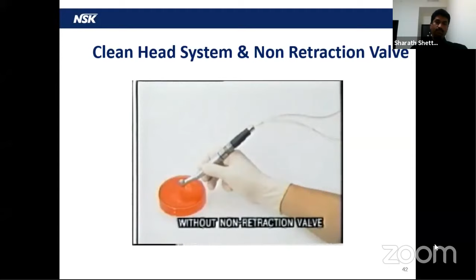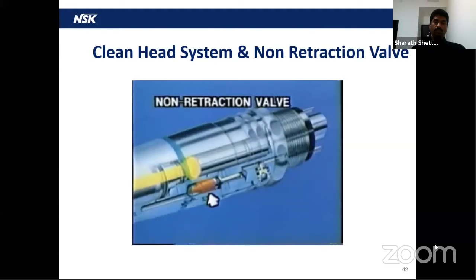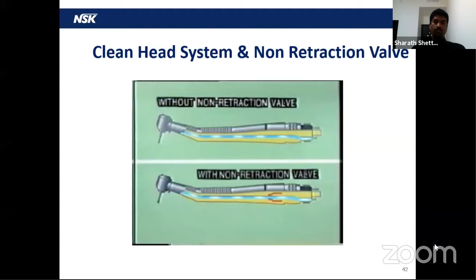The test you are now seeing is conducted without the non-retraction valve. You can see clearly, the retracted water, colored in red, is drawn back beyond the handpiece into the hose. Now look at the test with the non-retraction valve. The valve allows the water to pass in one way only. When pressure is applied in the reverse direction, the valve closes to shut the water from being retracted. The valve keeps foreign matter out and prevents water from dripping.